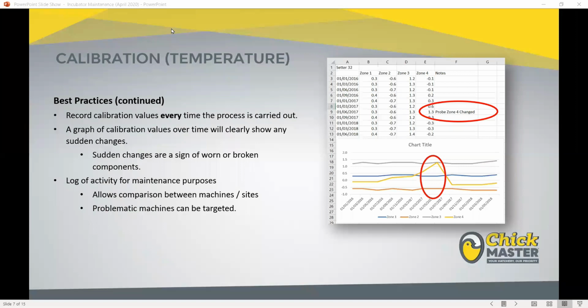Can we calibrate empty machines? You can calibrate empty machines, but you're not going to get a good reading. As part of the commissioning of the machines, we'll do an empty calibration, which is primarily to test the functionality of the calibration and make sure that there are no erroneous readings. But the problem with an empty cabinet, much like trying to calibrate a half empty Classic machine, is that the temperature stabilization of that cabinet is going to be all over the place. The egg mass itself, the sheer amount of fluid that's in a full machine, gives us that stability for the temperature control inside the cabinet. And that's what leads you to having great calibration values.